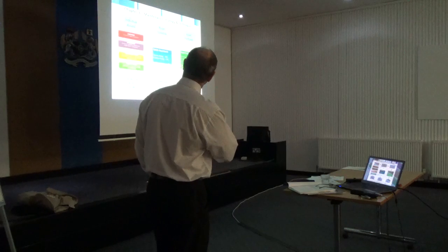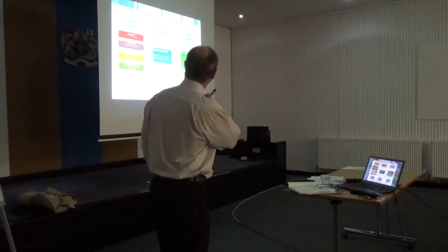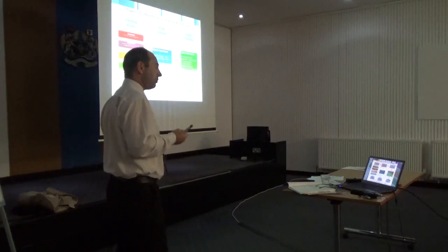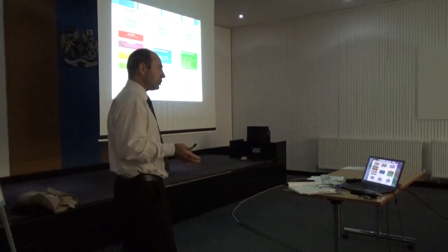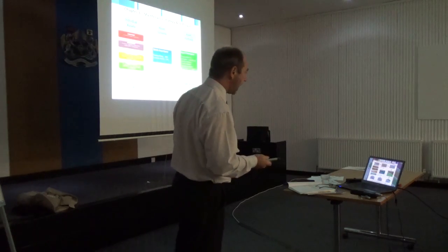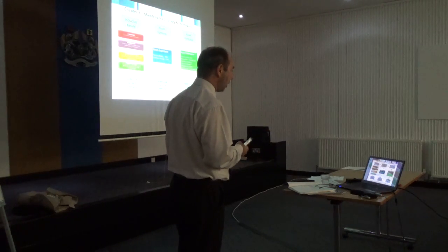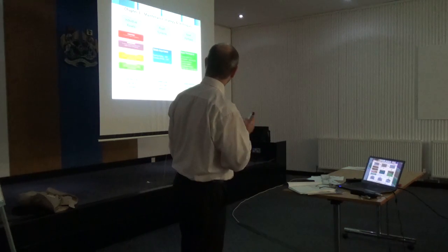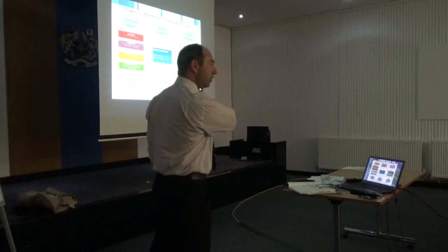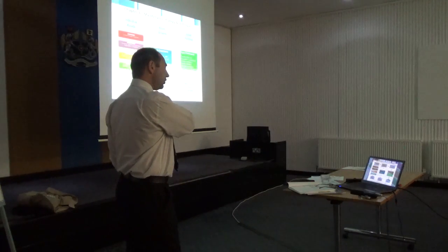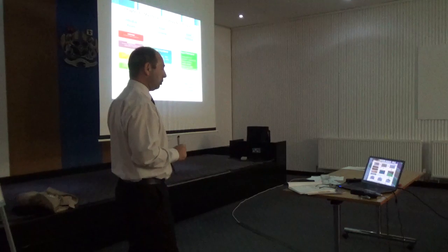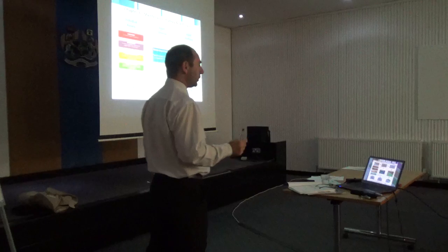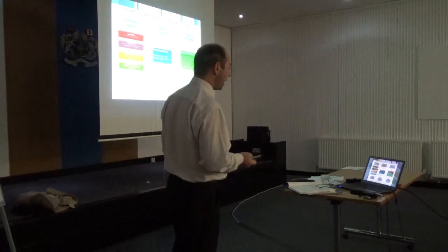So what I've also shown on the left here is again the way SFG20 is now being configured. You have essentially four types of maintenance. You have your statutory, mandatory, what's being called either business critical or functional critical or function critical. I don't like the word discretionary, but that's what we've called it. Discretionary maintenance, or routine is probably a better word. So the top two are really your compliance model, the must do, keeps you out of jail.